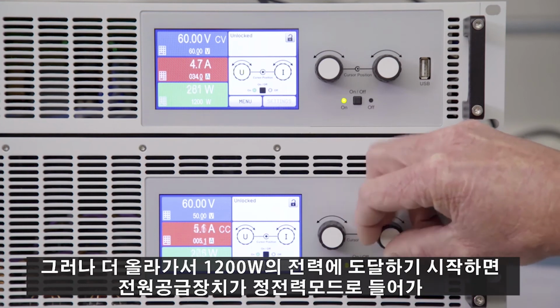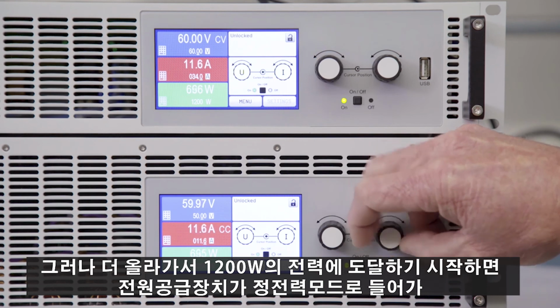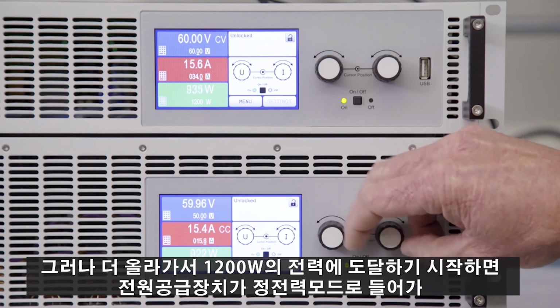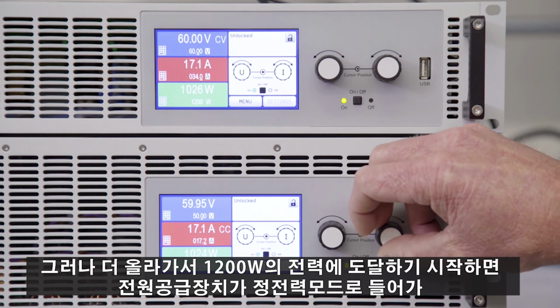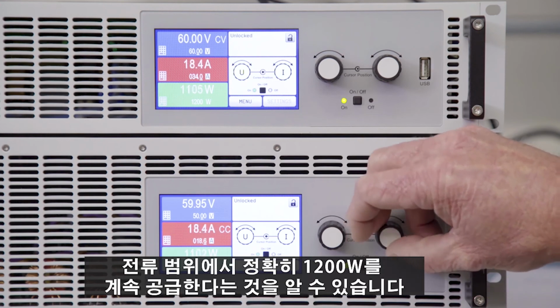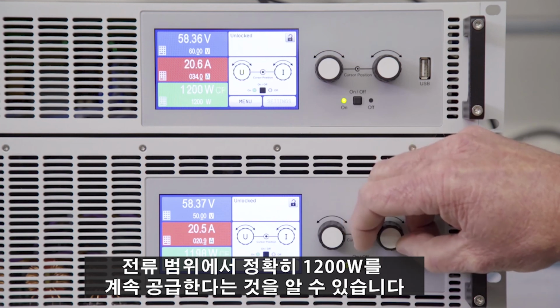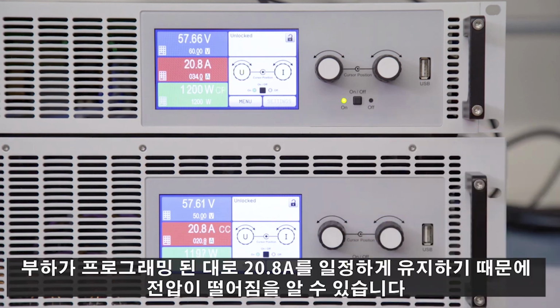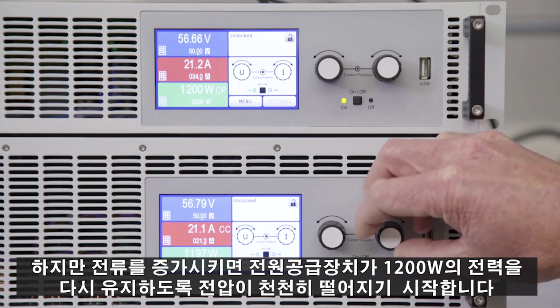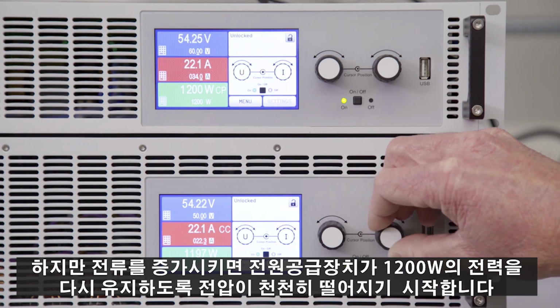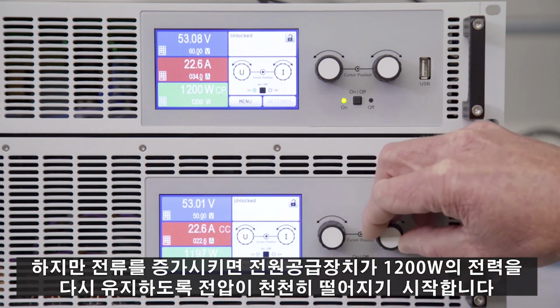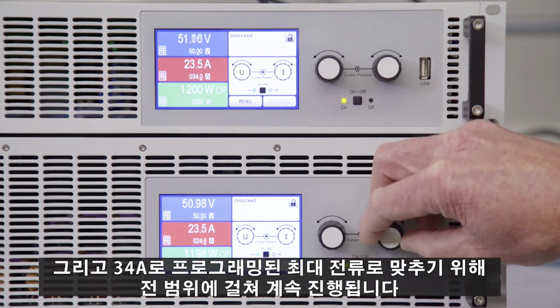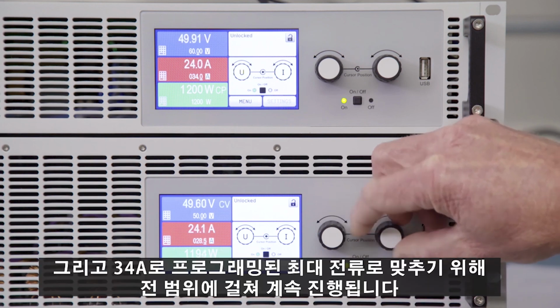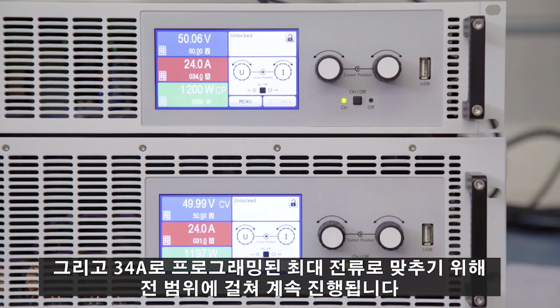But as I start to reach the power of 1200 watts, once I hit that 1200 watts, you're going to notice that the power supply is going to go into constant power mode and continue to deliver exactly 1200 watts across the current range. So we've now entered into constant power mode. You'll notice the voltage has dropped down because it's maintaining a constant 20.8 amps, which is what I programmed my load to. But then as I increase current, you'll notice that the voltage slowly starts to ramp down so that the power supply maintains, again, that constant 1200 watts of power. And it will continue through the entire range, all the way up through the maximum current that I've programmed, up to 34 amps.